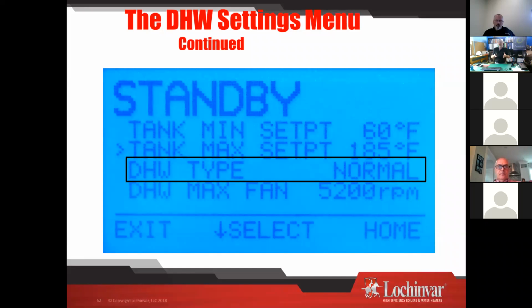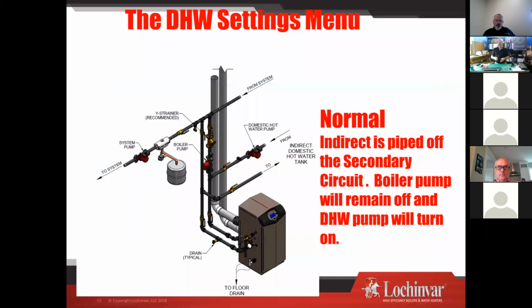Okay, so in that situation, I am shutting off the boiler pump, which you see right above the domestic hot water takeoff here, and turning on this domestic hot water pump. So I will not pump up onto the loop. Now that's the default setting for the boiler.